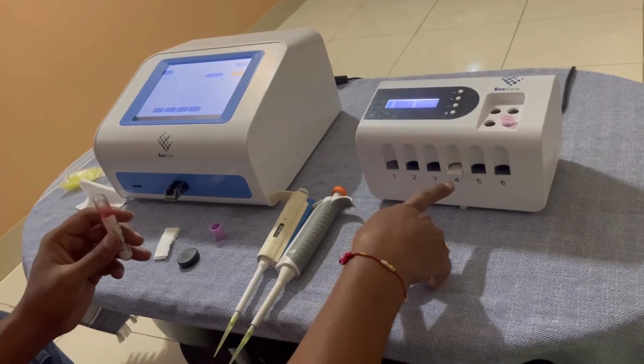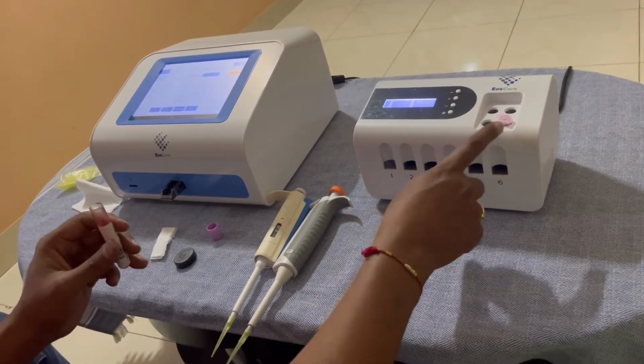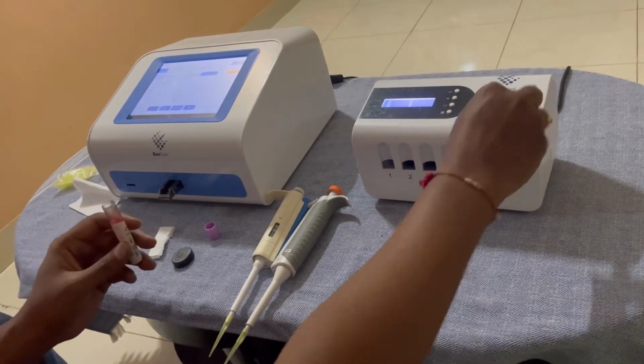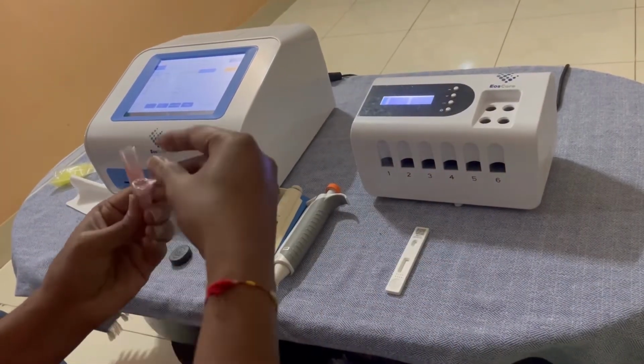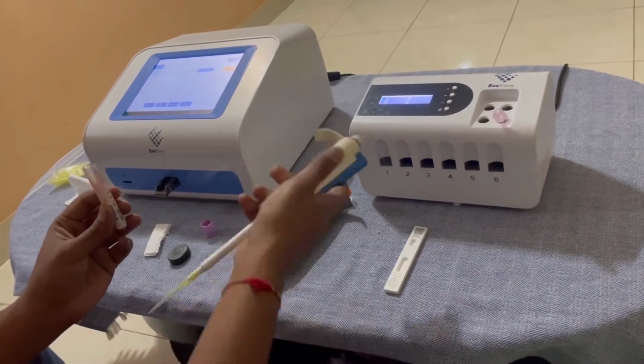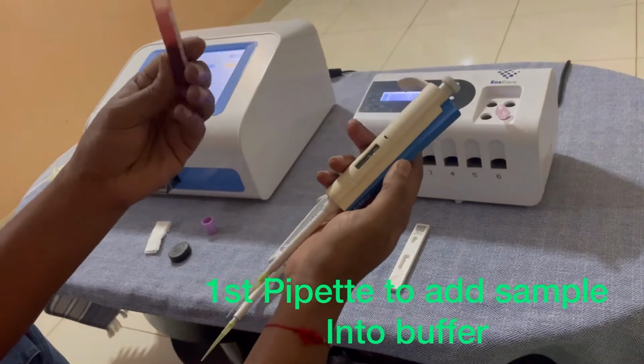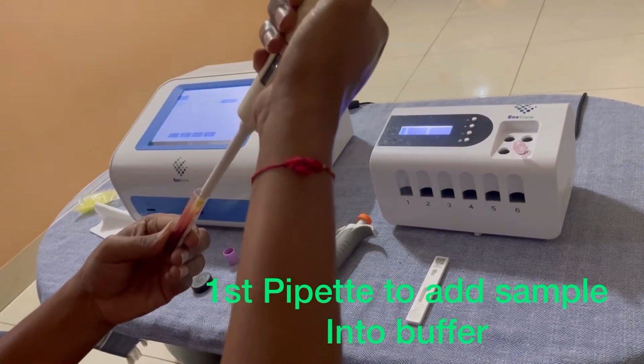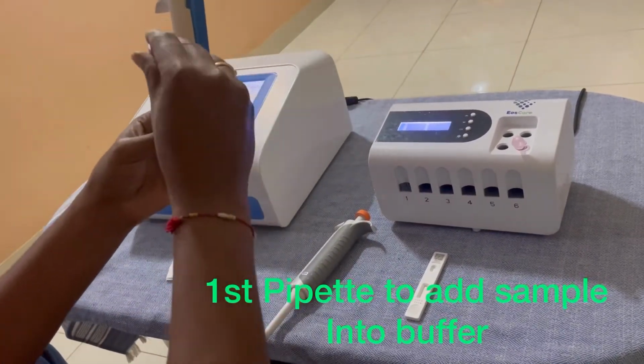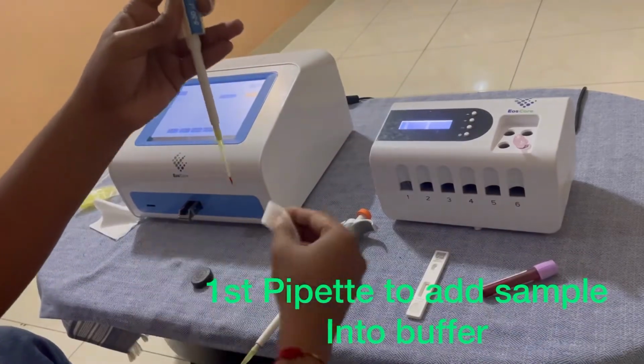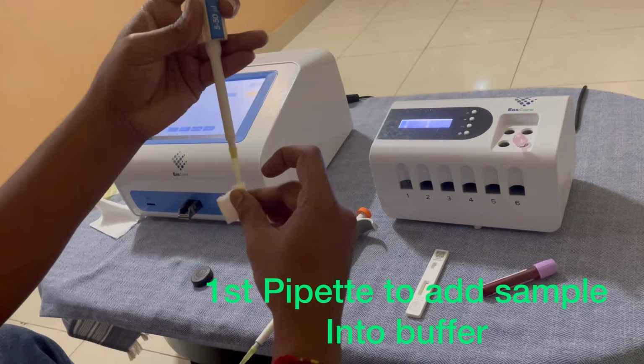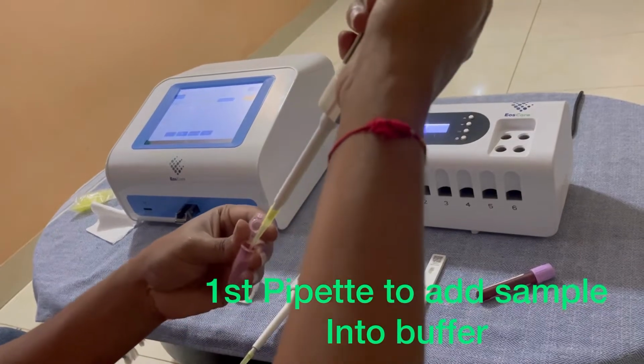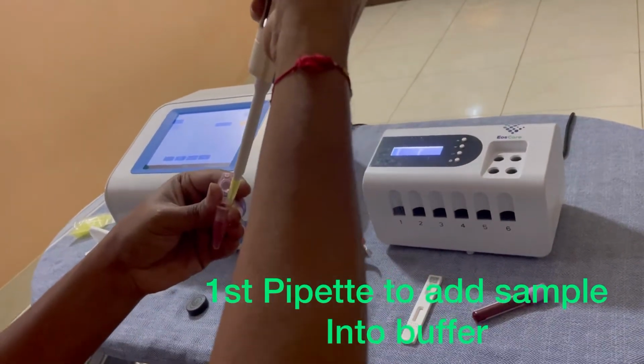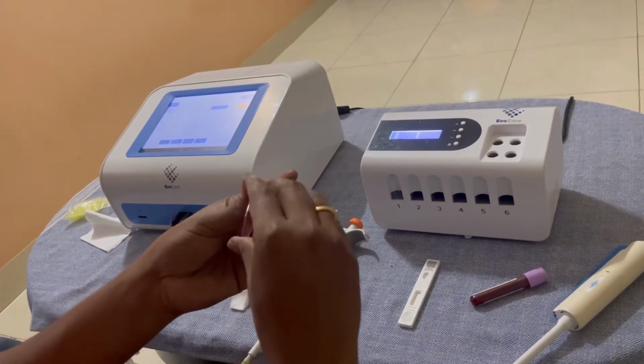So the 5 minute incubation is completed. That is, preheating is completed for the cassette as well as the buffer. So now we are running the test. We have taken a buffer. Now we are taking 5 microliter RBC for HbA1c. This is already mixed. Now I am taking it. You have to wipe it. Now mixing. Once this is done, you have to mix it for 1 minute.